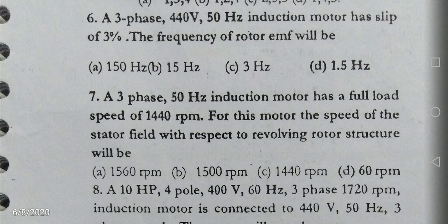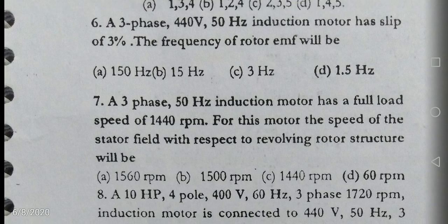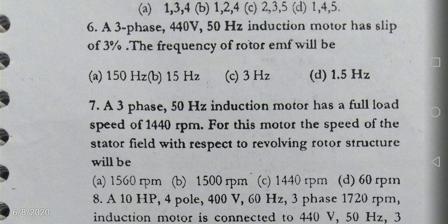The frequency of the rotor EMF will be, so the rotor frequency means it is slip times the stator frequency. So the slip is 3%, that is 0.03 into 50 hertz, that is 1.5 hertz.